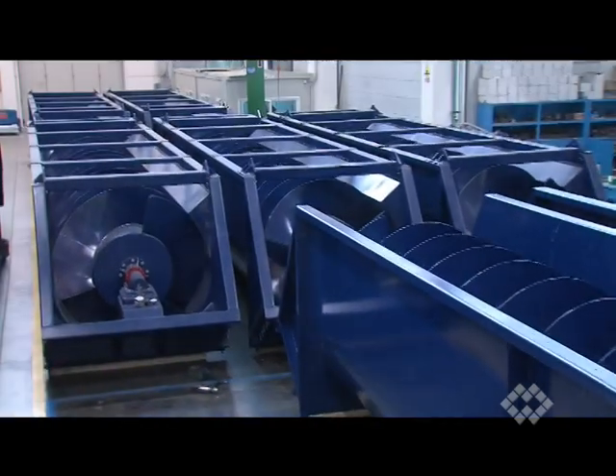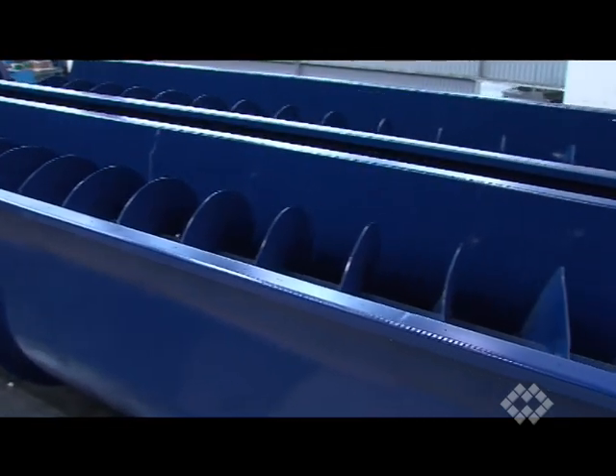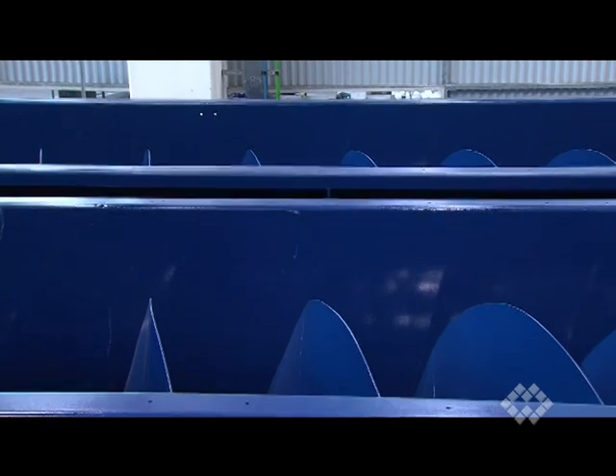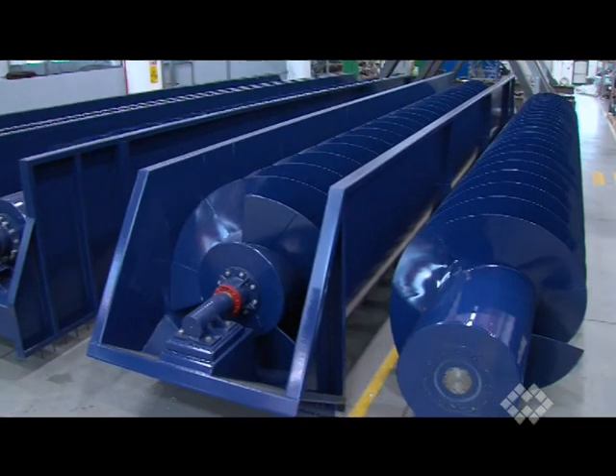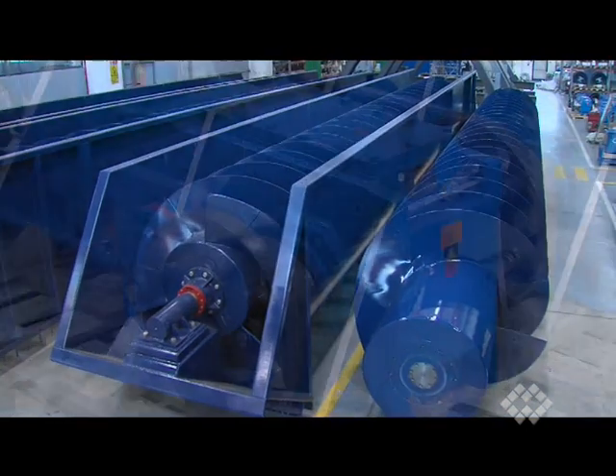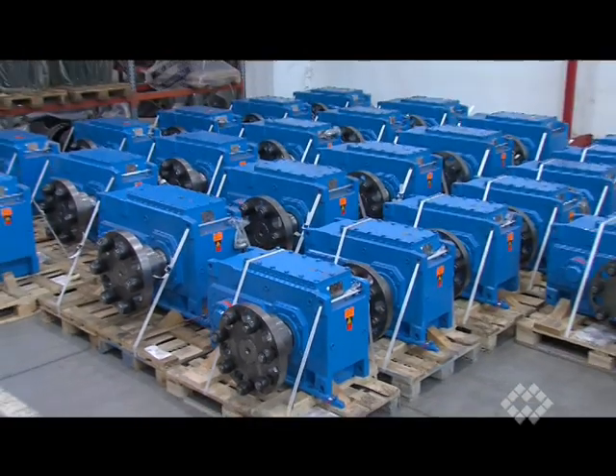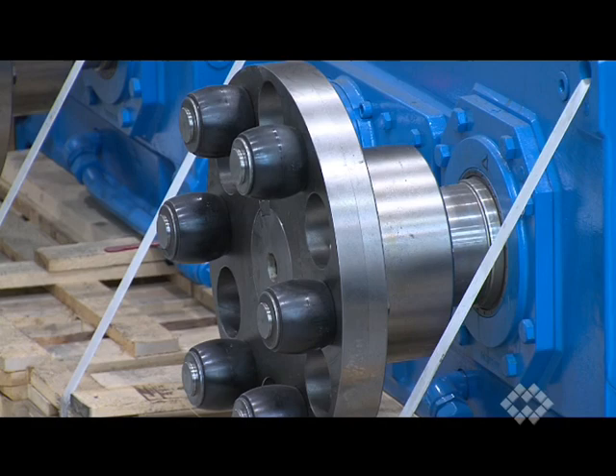The capacity is 3700 cubic meters per hour per each screw pump. All 25 screw pumps have diameters of 2 meters and different lengths going from 10 up to 19 meters. The weights go from 15 tons up to 23 tons per screw pump. The screw pumps are supplied with three different power rates: 75, 90, and 110 kilowatt.